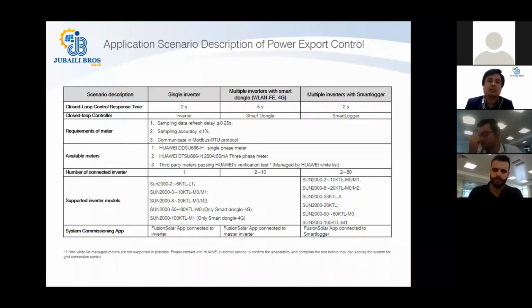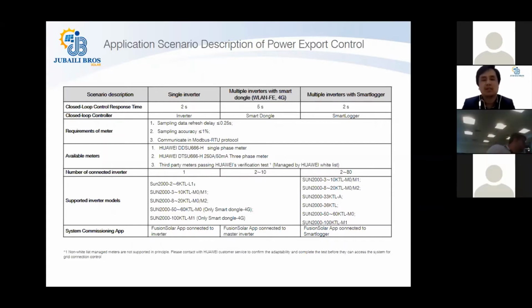With multiple inverters, you might have up to 10 inverters in a project. You may have the option of using a smart dongle in that project to do the power export control. Similarly, with multiple inverters, you might use a smart logger when the case is less than 10 inverters or beyond 10 inverters. In such cases, you have the option of using a smart logger as the point of closed loop control. There are certain power meters listed in the Huawei smart logger manual. If you do not find it, we can give you separately as an Excel sheet or a PDF, which encloses all the power meters that you can use to do the zero export control.